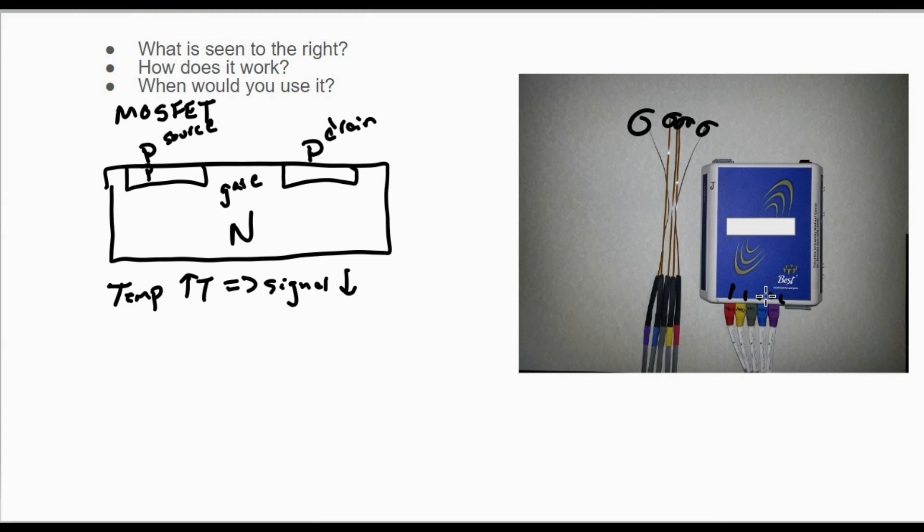At some point, you're probably going to have to replace these. I mean, look how delicate they are—they're fairly sturdy for what they are, but you may have to replace them. And there is angular dependence, because depending on where the beam is on or coming in at an angle, that may affect the radiation hitting this P-type semiconductor.